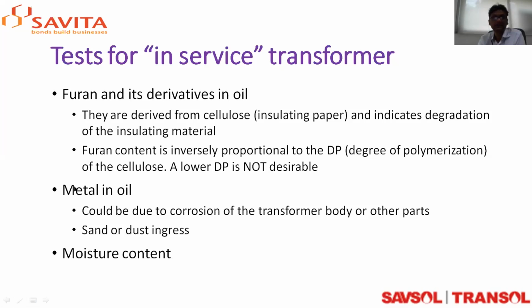Moisture content: whenever you take a sample of an in-service transformer, you have to measure the moisture. An increase in moisture suggests that there is a leakage somewhere in the transformer, in the case of a non-breathable transformer. So one can attend to these leakages and restrict the moisture, because any increase in moisture is going to hamper the quality of the paper over time, and ultimately it is going to reduce the life of the transformer. Next slide.